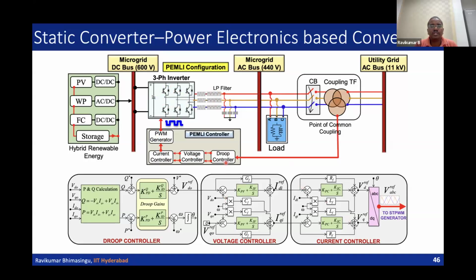Here you can see the droop controller, with VD naught, VQ naught, ID naught, and IQ naught. These are measured, and there is a PQ calculation for active power and reactive power, which is then compared with the reference values. Using these KP, KI droop gain functions, it will generate the VD reference and omega.